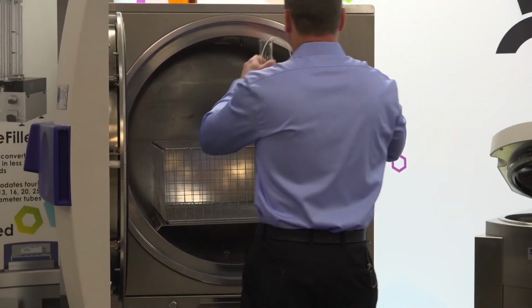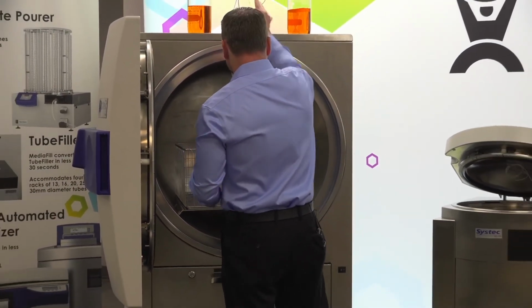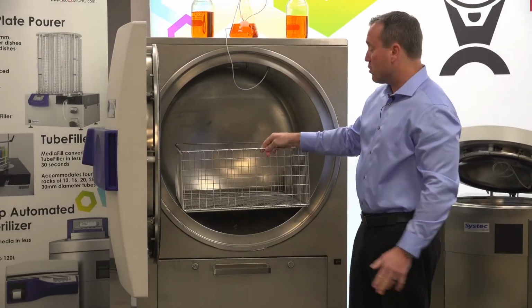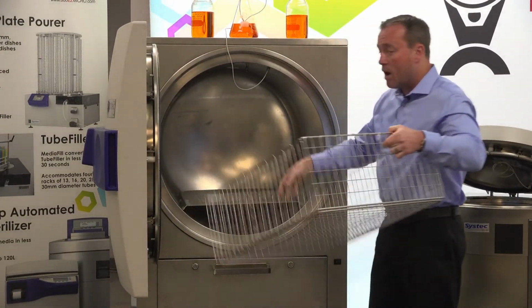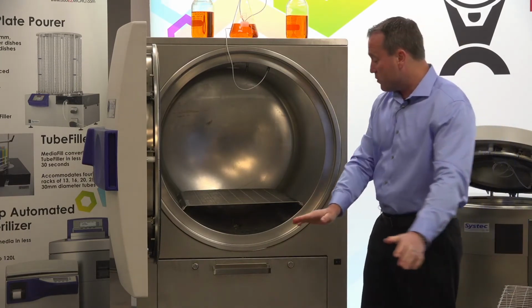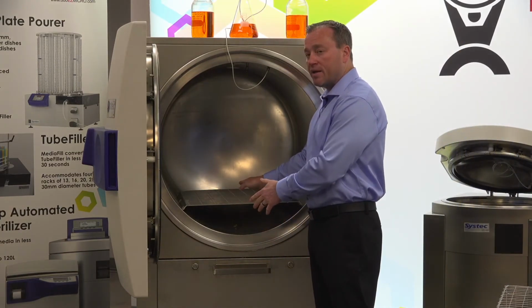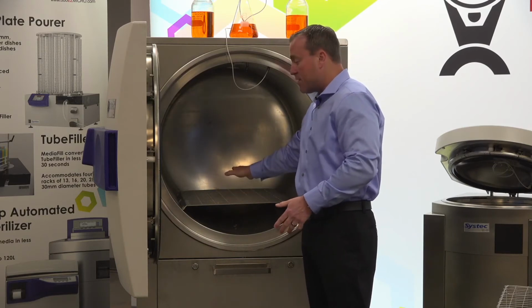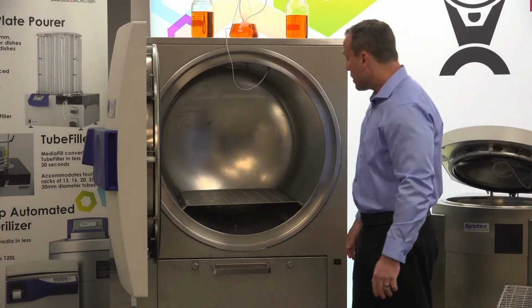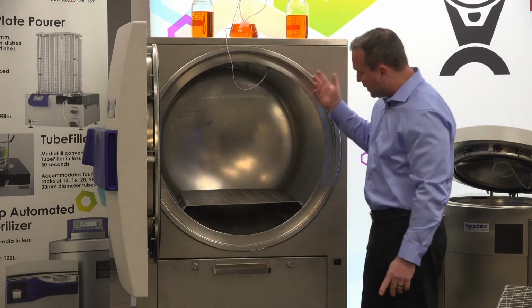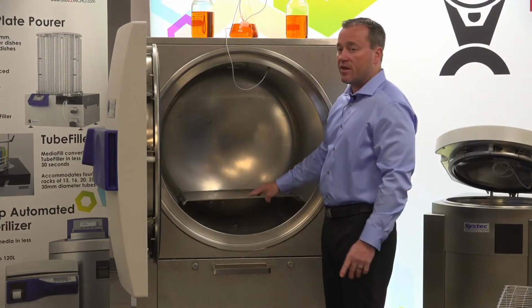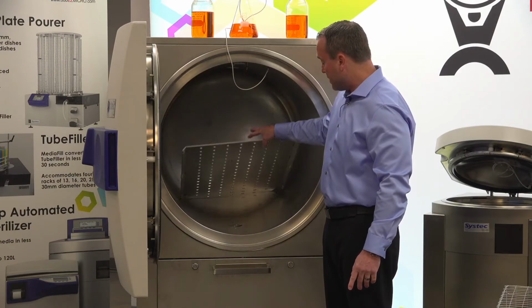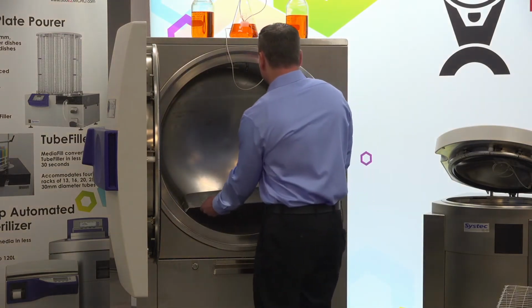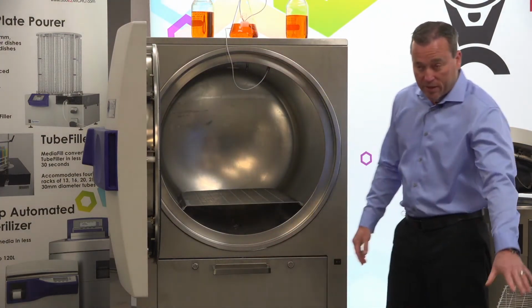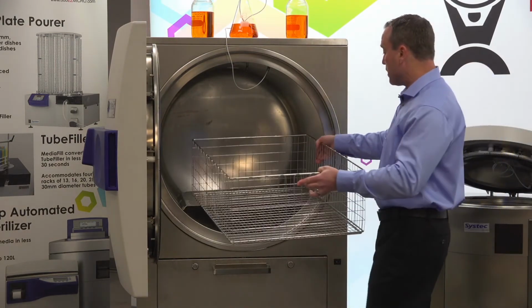So I'm just going to take these out, set that up there. So we do have loading trays for this instrument. So this one I just have a basket in here, but we also do offer loading trays that would allow us to come right up and then load directly into the system. So it would lock into place and then just go directly back into the unit. And what you can see in here is a really nice clean vessel, no heating elements or anything inside. So a really nice system, really clean, and able to do several different types of applications. Just going to throw these back in here.